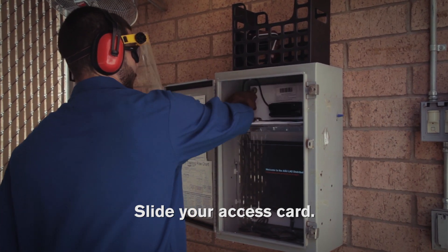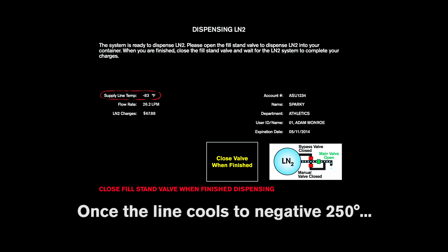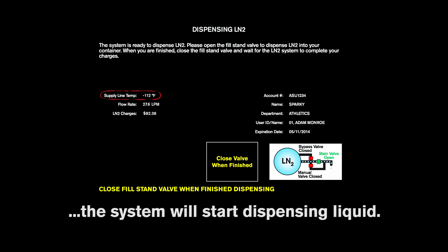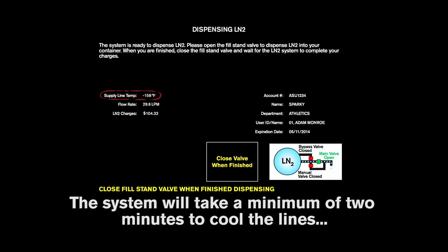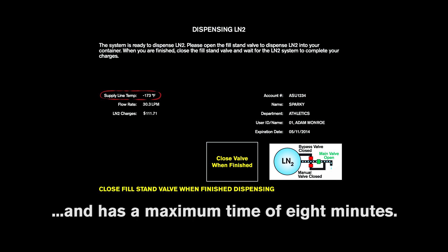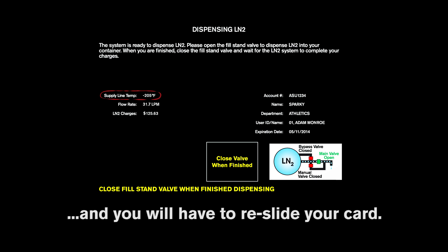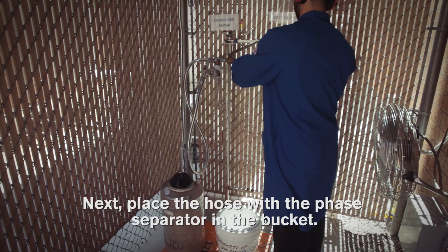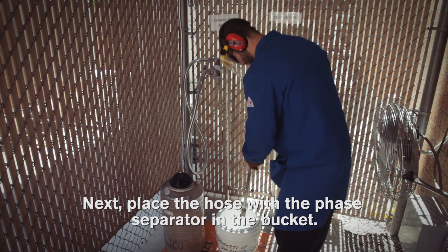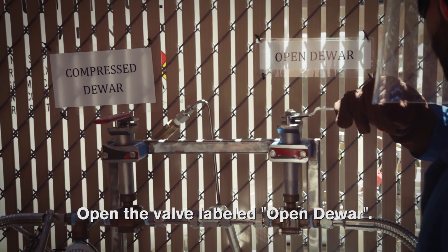Slide your access card. The display will show you the line temperature. Once the line cools to negative 250 degrees, the system will begin dispensing liquid. The system will take a minimum of two minutes to cool the lines and has a maximum time of eight minutes. Once the system has reached eight minutes, it will automatically shut down and you will need to re-slide your card. Next, place the hose with the phase separator in the bucket.